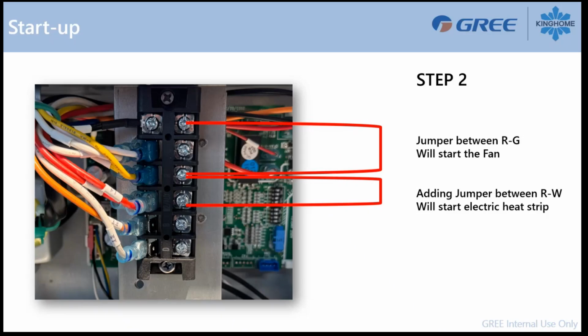There's no wait, it will start right away. There's no delay, or maybe a couple of milliseconds. Whenever you apply power between R and W, and the blower motor is already running, your duct heater will start without any delay.